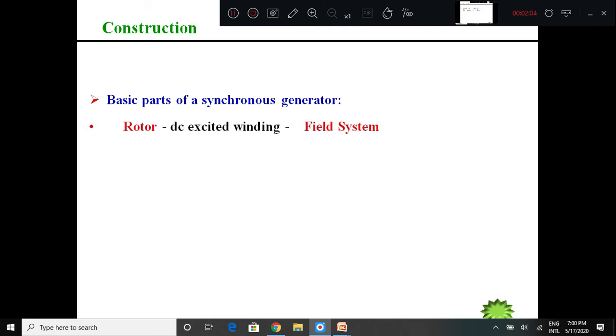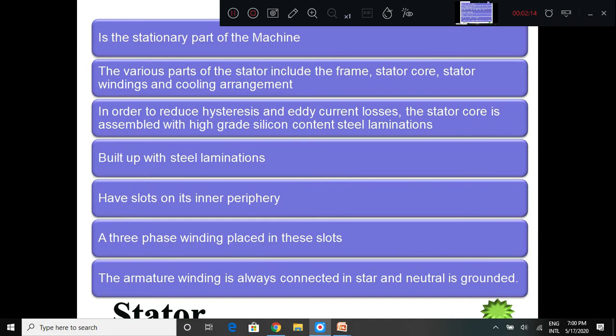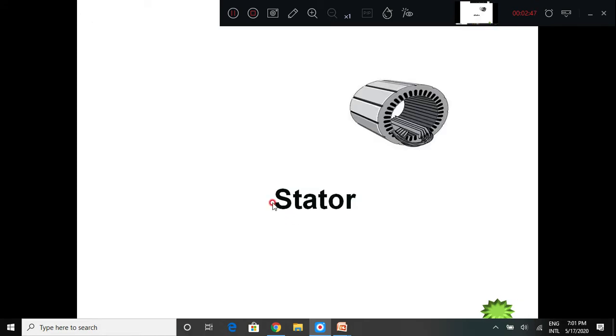The basic parts of the synchronous generator are the rotor - that is the field system - and the stator, which is a three-phase winding where the generated voltage is produced, also called the armature. The stationary part of the machine, which is the armature, consists of conductors connected in three different windings R, Y, and B. The stator is also made up of laminations to reduce eddy current and hysteresis losses.